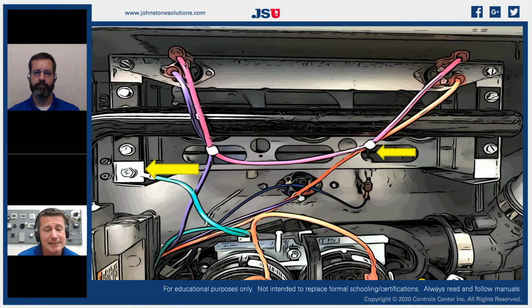And we get leaks in our seals because we have a lot of expansion and contraction going on between dissimilar metals. Typically, we got our ABS draft inducer or our steel draft inducer sitting up against a galvanized or a standard steel collector box with a gasket in between, and we get some expansion and contractions. So we do get some condensation sometimes leaking out of those. Very acidic condensation that will absolutely create corrosion on that burner box. How many times have we seen a burner box that's got a rusted top plate to it, right? What's rust? It's an insulator.